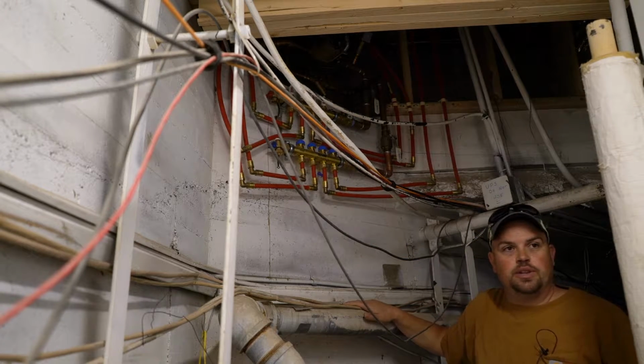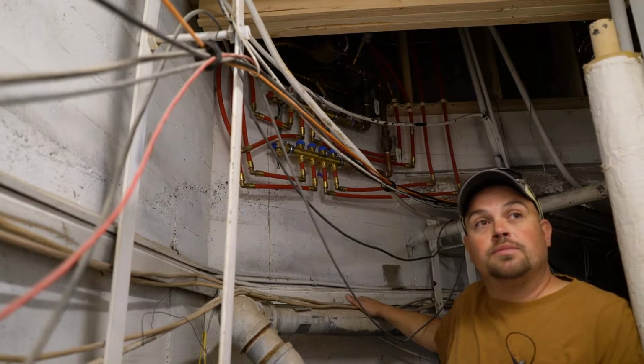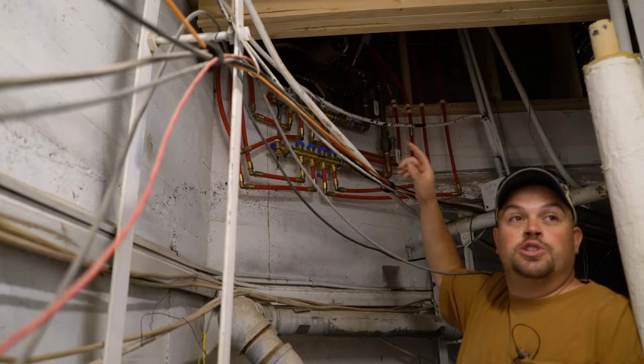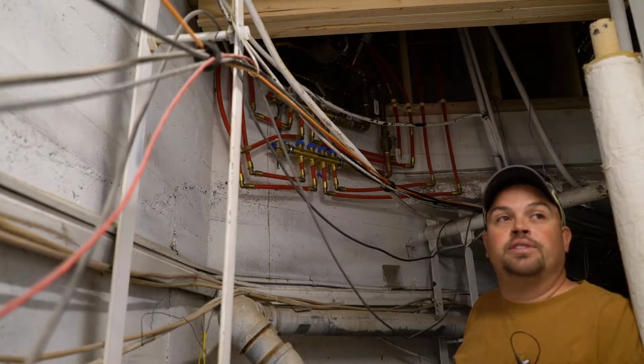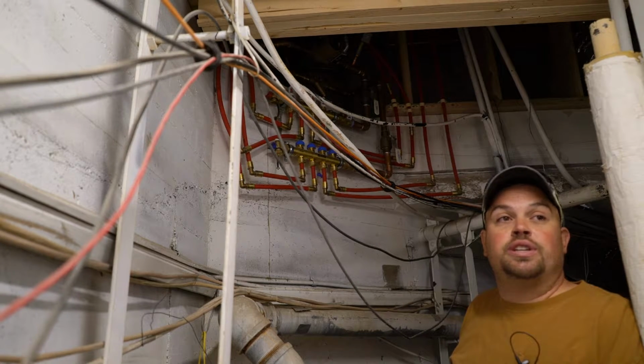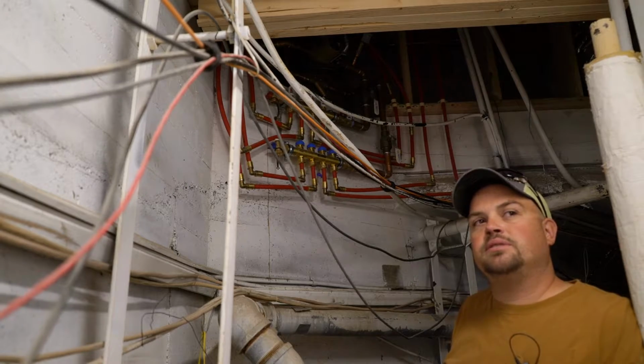Is this manually turned on in the winter? It's on. It's got its own control valve from Johnson Controls. So when the temperature drops, it'll kick on. We don't have to shut it down in the fall. You shouldn't have to, no. There's a glycol concentration in this system. Yep, I think it's 35%.